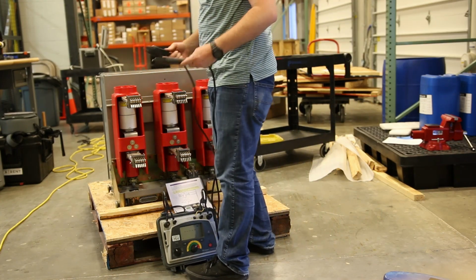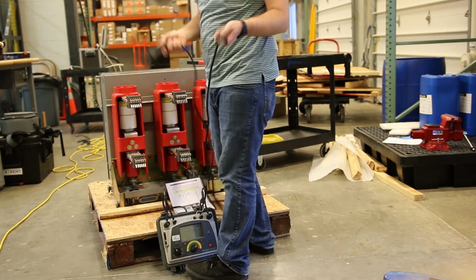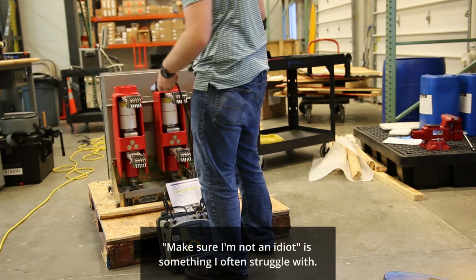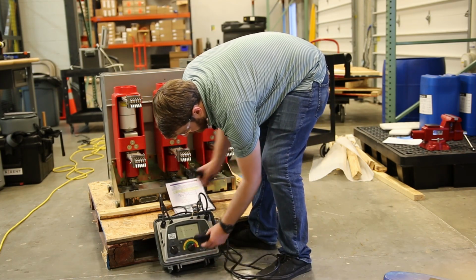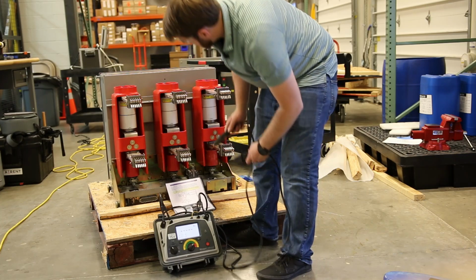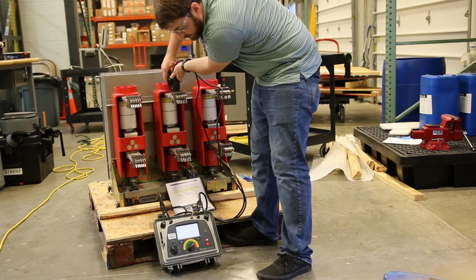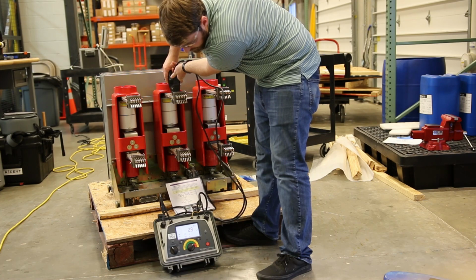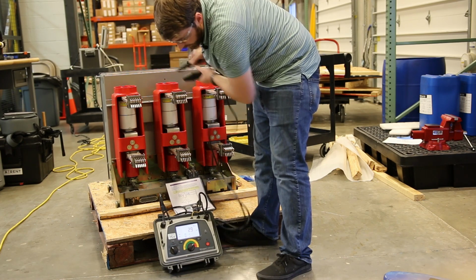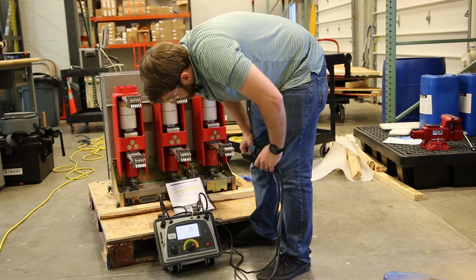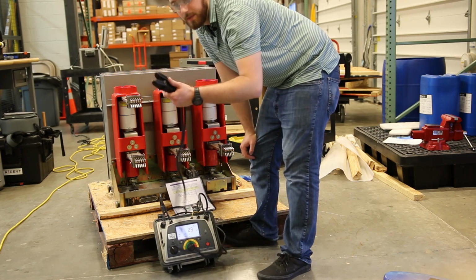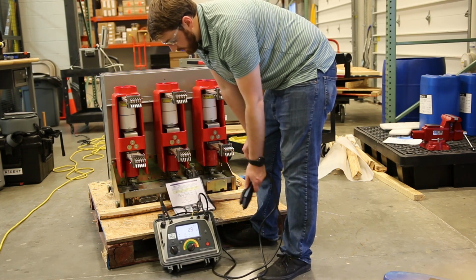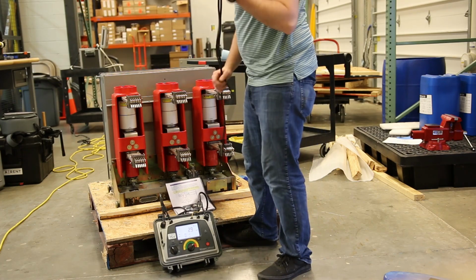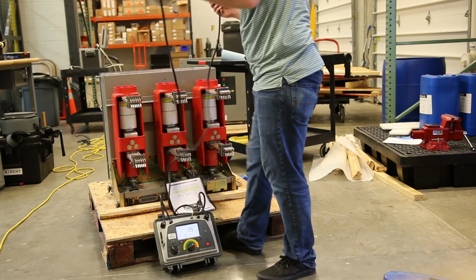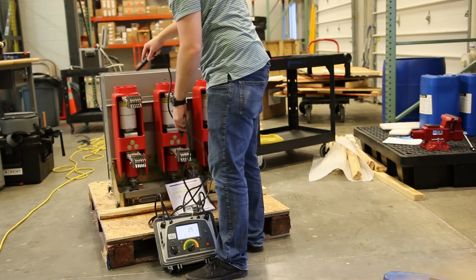One thing that I like to do when I start testing is just make sure I do an idiot check. I make sure I have everything hooked up right. So we're gonna try and get this so we can both see it here. That makes it almost impossible. I try to make it so that we can verify that our test leads work. So I'll go on a single piece of copper. And this says I got 2.9 micro ohms. So the lead resistance essentially is 2.9 micro ohms. So I know that my leads are good. That's a tiny, tiny amount of resistance, like millionths of an ohm.